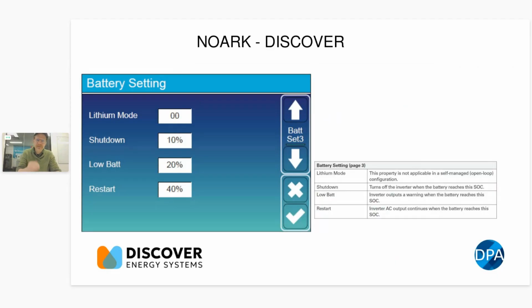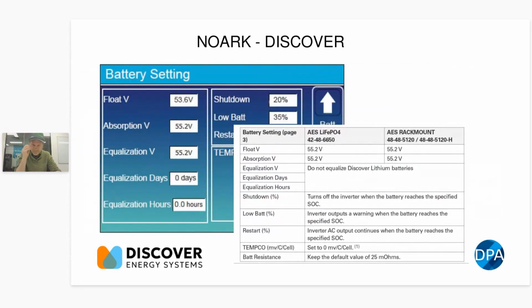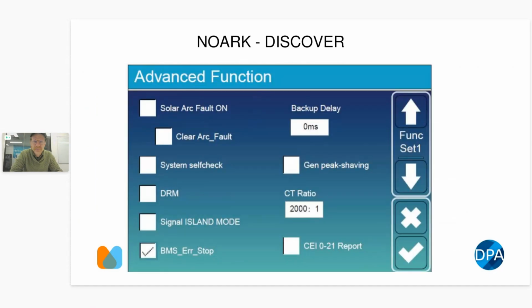We're running out of time, so I'm going to go through these pretty quickly. You're going to set up your low disconnection voltage, state of charge, and reconnection state of charge as per normal in here. And like I said before, don't go below 10%. It's just good system design. If you're running an open loop, then you've got to use these normal voltages as you would with any other open loop system. In the Noark, it's really important to have the BMS error stop switched on. That basically means that if it loses comms, it stops instead of keeping on doing whatever the last message was. So that's really important for these lithium batteries.